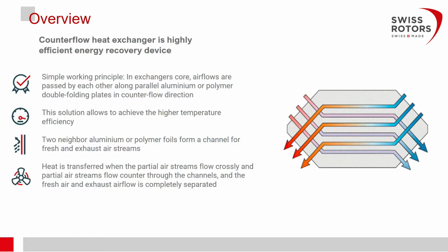Some overview and base information about this Counterflow. You can see the picture on the right side. This is the difference from the cross flow, in the middle part of the exchanger. The rest is more or less the same. And now, what does it give to us? Simple working principle: in the exchanger core, the airflows pass each other in the nearby channels. And the channels are closed by double folding plates all together in order to secure tightness. And this Counterflow direction of the exhaust and supply air gives us the highest possible efficiency.